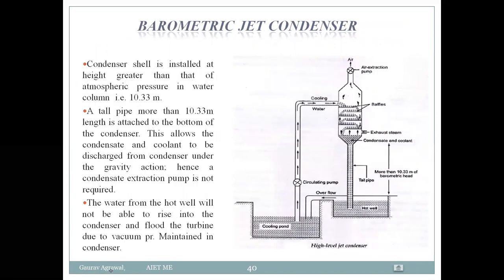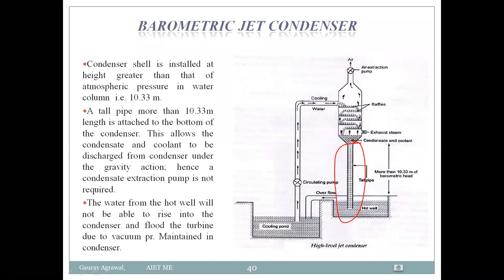Next is the barometric jet condenser. In this type, the condenser is installed at a height, and a pipe of 10.33 meters is created. This pipe height of 10.33 meters is significant because it corresponds to the atmospheric pressure equivalent in a water column.